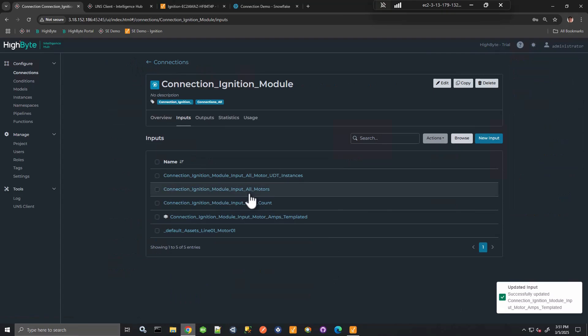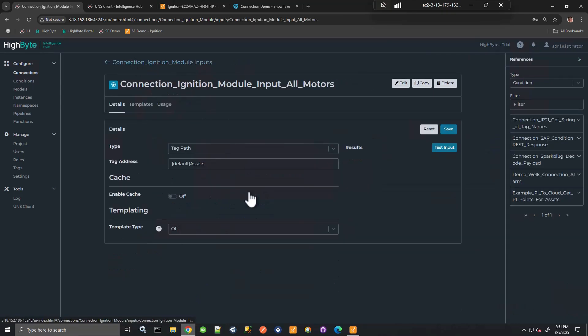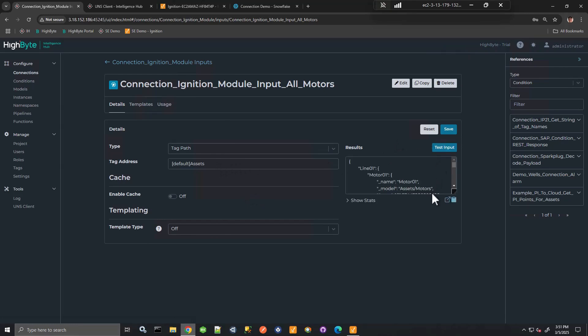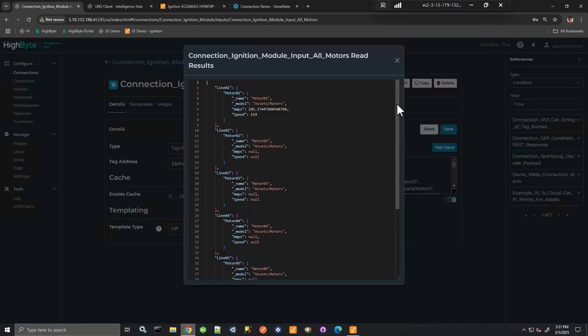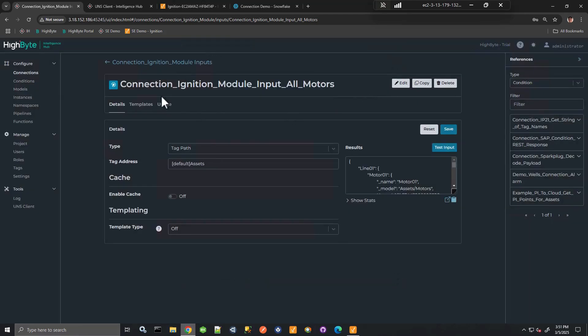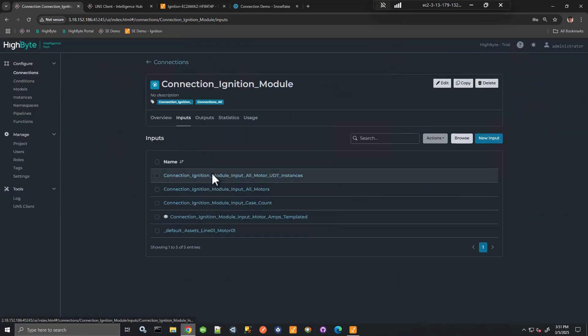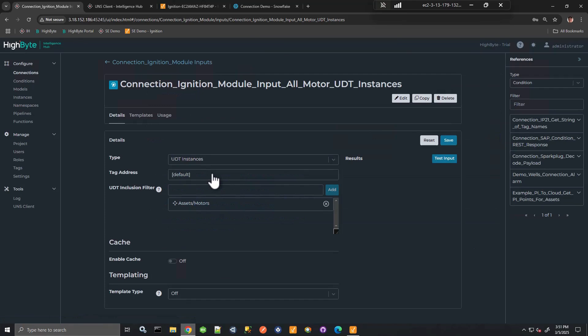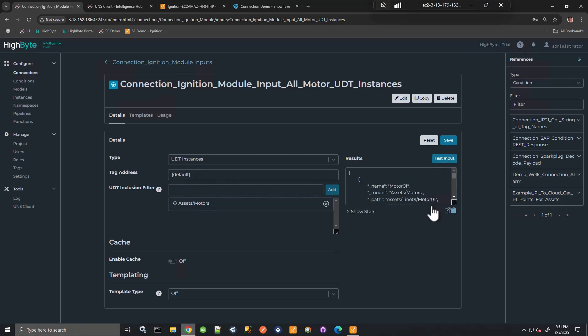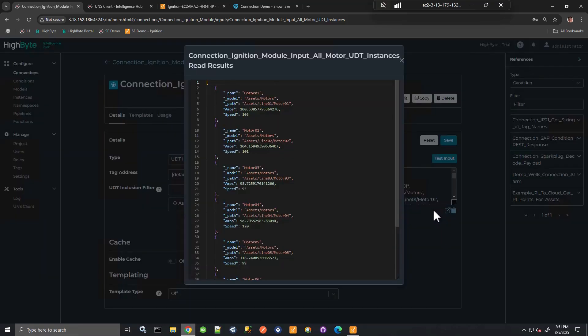So this is pulling back that array. And then also, I can pull back at a higher level of the namespace and obtain the hierarchy and things that have been defined in Ignition. And we also can search by UDT. So I can search by, I can filter. So this is my motors UDT within this tag provider. And here I can search. And what this is going to do is pretty valuable. So this is an array containing the process values for those, for the motor as defined by the UDT.